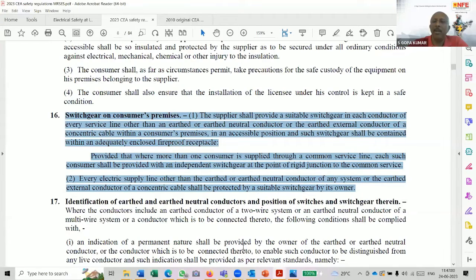So will it be doubled? But sir, in 16 it is belonging to the supplier, and in 20 it is by the consumer. Yeah, sir, the interpretation can be that the supplier has to provide a switchgear, and in addition, the consumer also has to put one more switchgear. So then it becomes double. Before the point of supply and one at the point of supply. So that is a distinction.